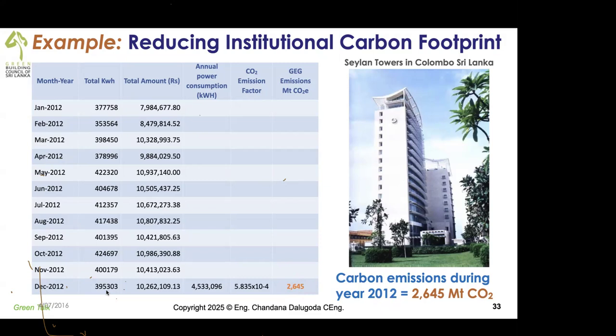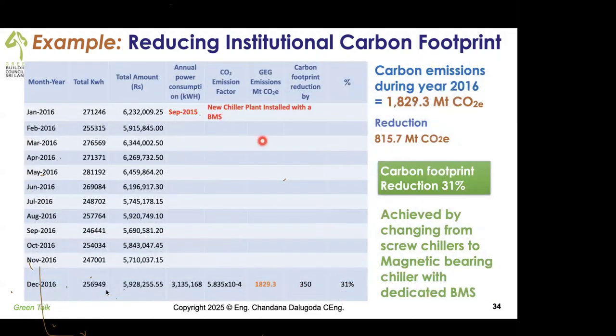Now, 2015. This building has screw chillers. The efficiency in 1994 was 0.84 kilowatt per ton. But it was replaced with a very advanced chiller. These are all full load values, 0.5 kilowatt per ton, something like that. Just an example. And their part load values are very much lower.